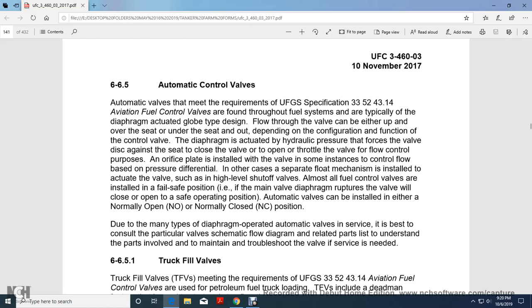The diaphragm is actuated by hydraulic pressure against the force of the valve disc against the seat, to open the valve and throttle the flow. A control orifice plate is installed with the valve in some instances to control the flow based on the pressure differential. Where separate float mechanisms are installed, they actuate the valve, such as a high-level shut-off valve. Almost all fuel control valves are installed with a fail-safe position. If the diaphragm ruptures, the valve will close or open to a safe operation position.